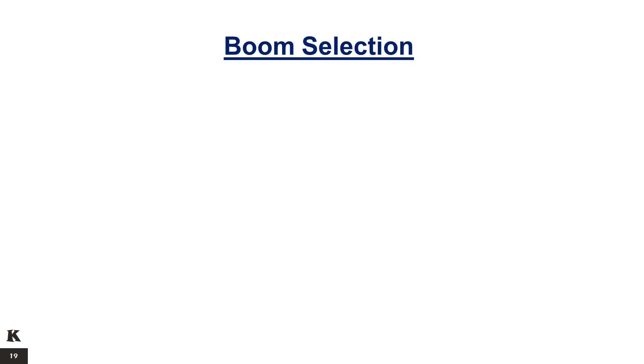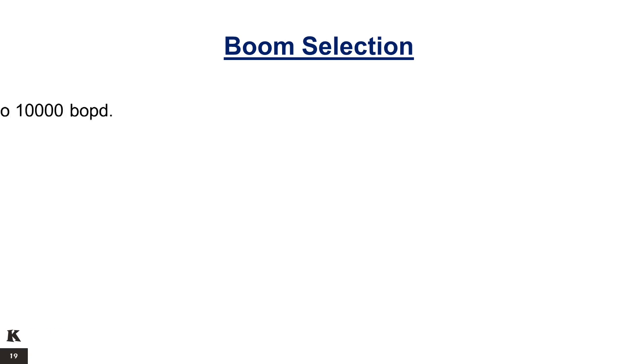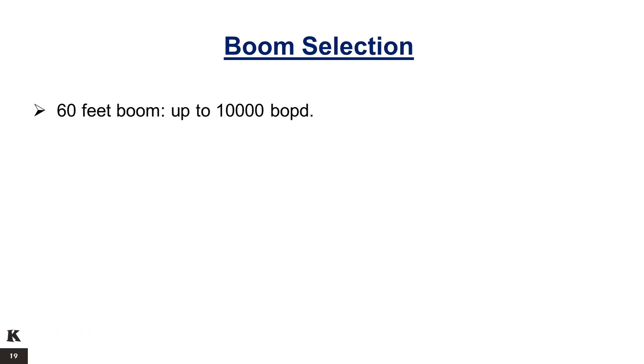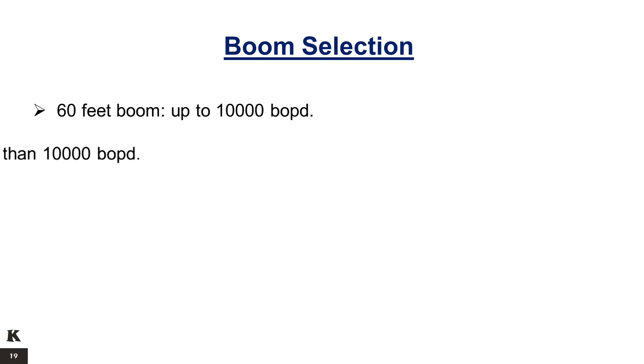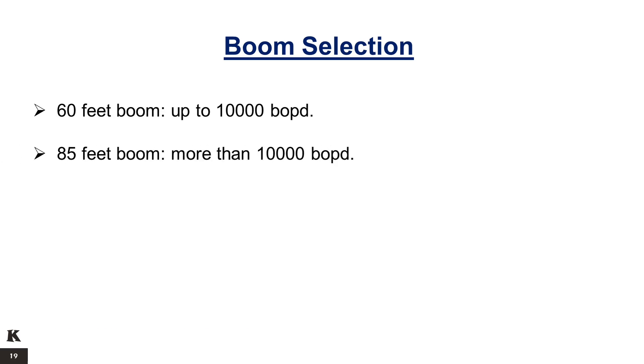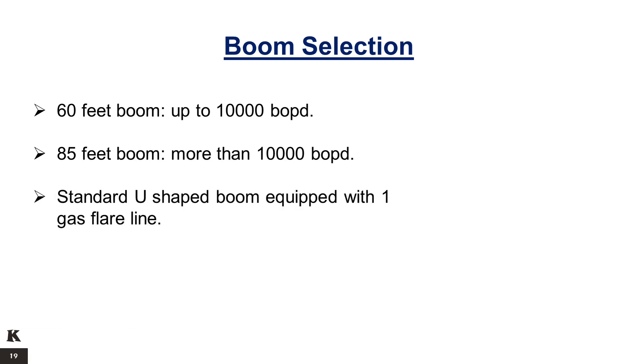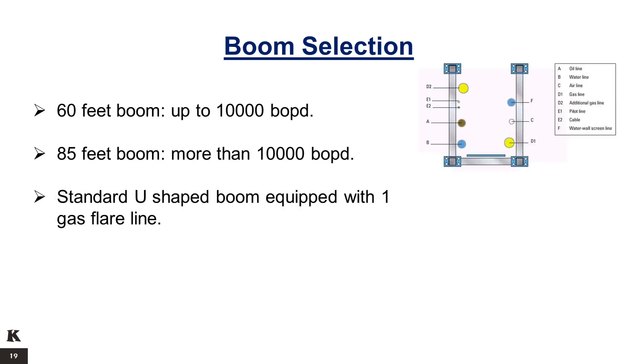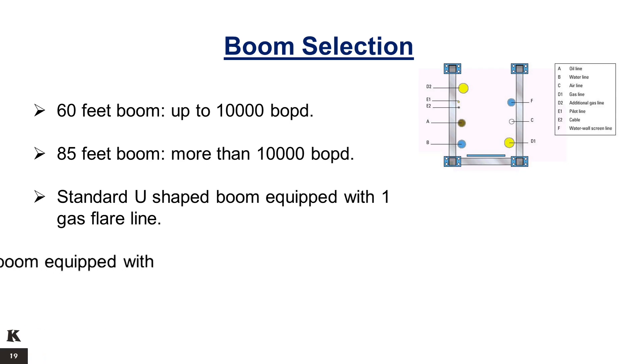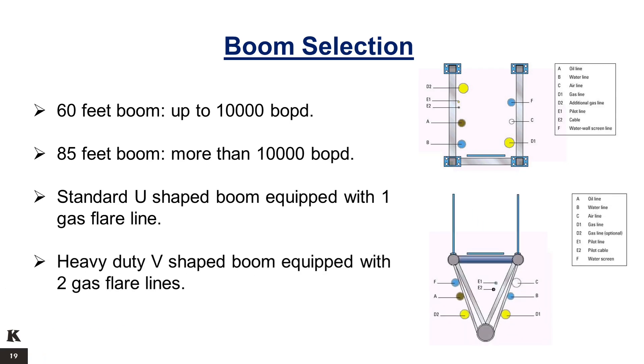Boom Selection. A 60-feet boom may be used for a flow rate up to 10,000 barrels of oil per day. An 85-feet boom may be used for a flow rate more than 10,000 barrels of oil per day. A standard U-shaped boom is equipped with only one gas flare line, while a heavy-duty V-shaped boom is equipped with two gas flare lines.